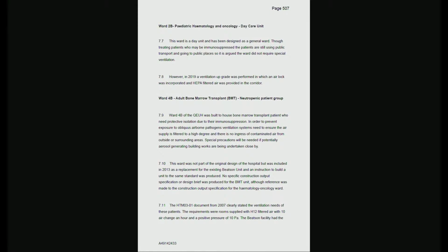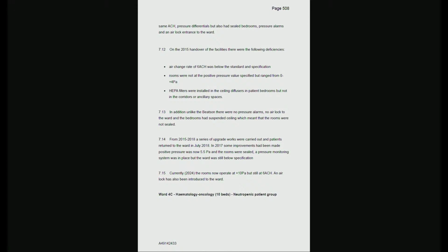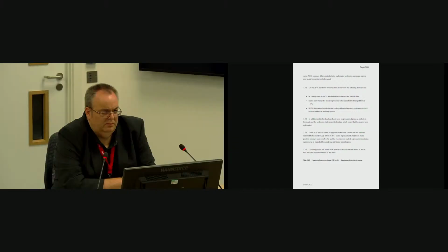You identify a series of deficiencies on page 508: the air change rate 6, rooms not at positive pressure, HEPA filters in patient bedrooms but not in corridors, no pressure alarms, no airlock, and suspended ceilings meaning rooms are not sealed. You understand some works have been done to that area - has that removed all the deficiencies you identify? I don't believe it's removed all of them. It's still operating at a lower than ideal air change rate, and as I understand it, there are also still areas with suspended ceilings present. I also haven't seen the full information on air permeability testing.